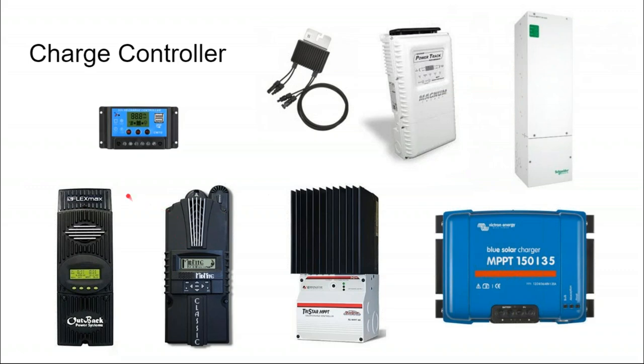The most cost effective charge controller on the market that I've found so far is able to take advantage of a 300 volt standard, so it's probably the more preferred one as well. Just be aware that you can get charge controllers at different voltages, and that might mean that you've been designing solar arrays where one 8 kilowatt array only has three circuits on it.